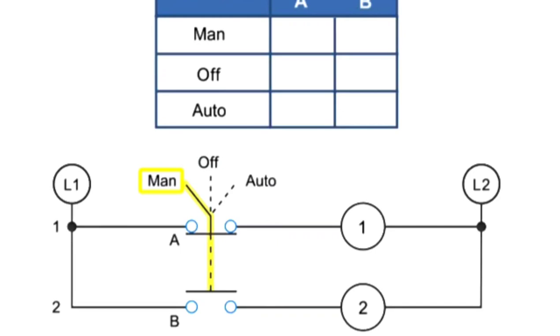Thus, in the MAN position, A is X or closed, and B is O or open. At the OFF position, both A and B are O or open. With the selector switch set to AUTO, contact A is O or open, and B is X or closed.